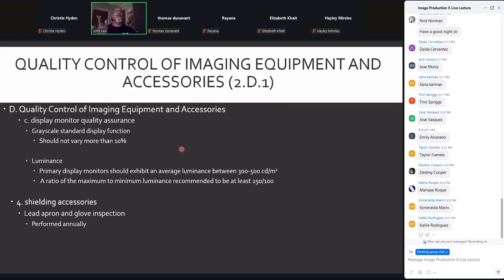Display quality assurance: the grayscale standard display function should not vary by more than 10%. Luminance is on a previous slide. Recommended luminance for a primary display monitor should be between 300 and 500 candela per meter squared. The ratio of maximum to minimum luminance should be at least 250 to 100. And then for our accessories, our shielding, lead apron, and glove inspections should be performed annually.